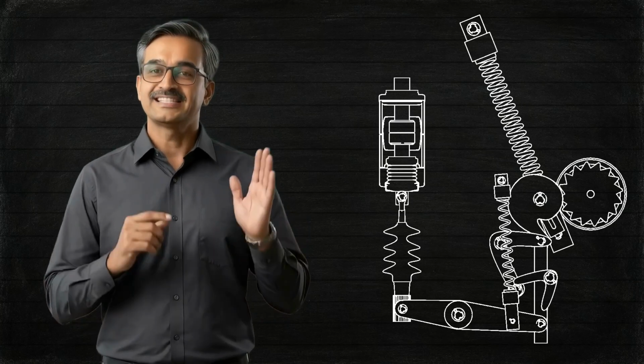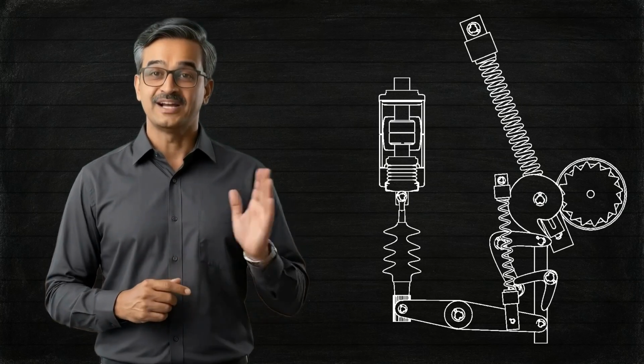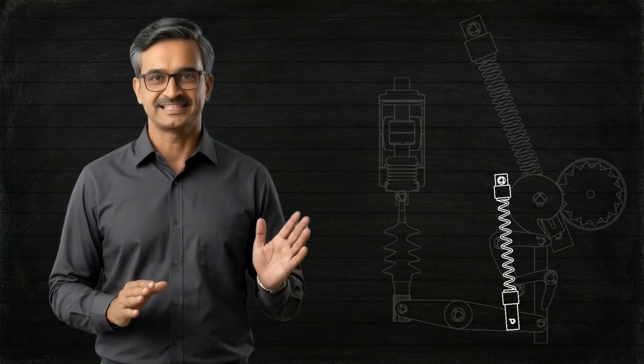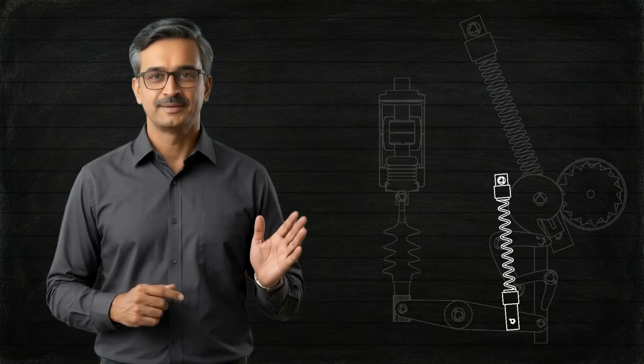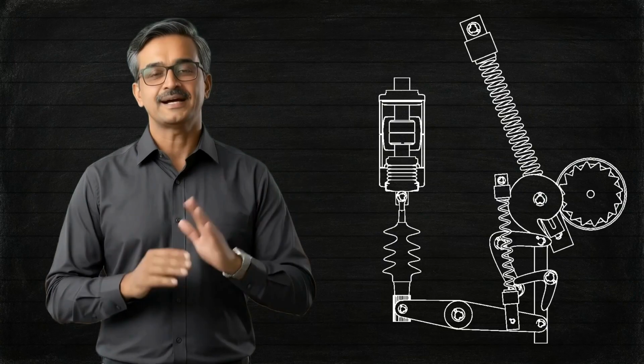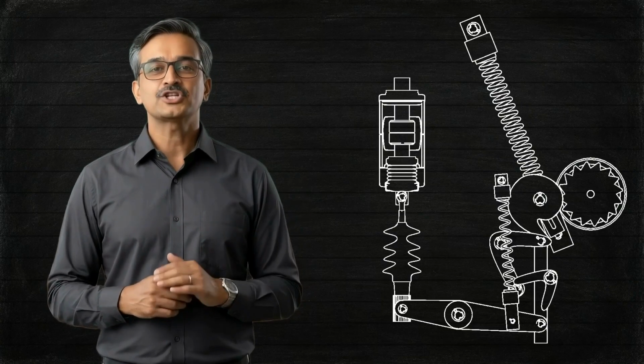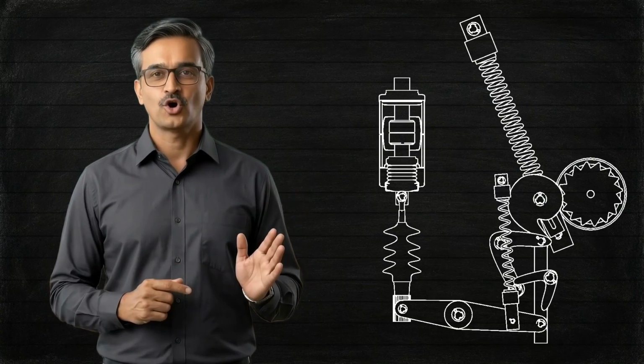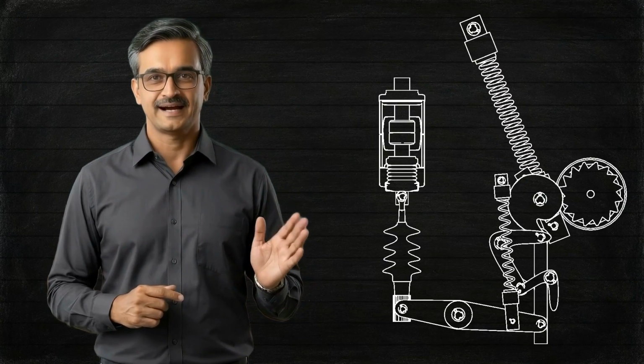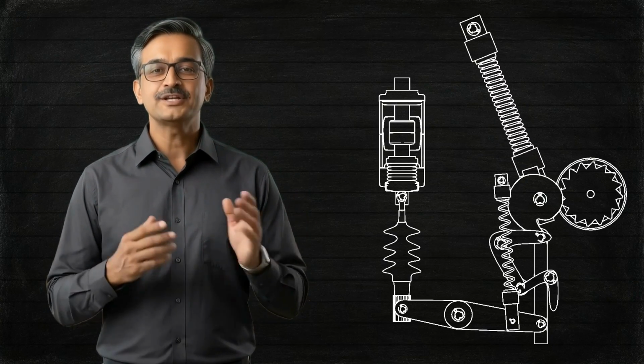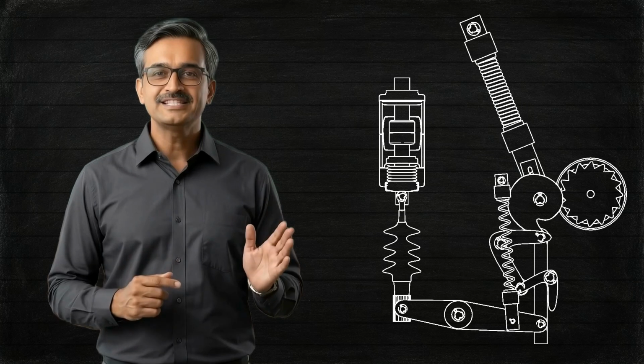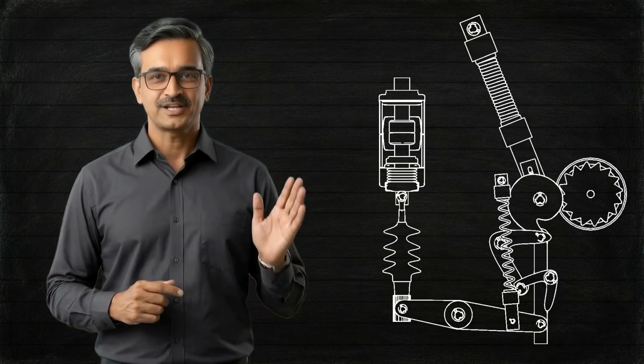But something very interesting happens during this closing movement. As the moving mechanism travels, it simultaneously compresses the second spring. This is the opening spring. So immediately after the breaker closes, the opening spring is fully charged. Then, a limit switch automatically starts the motor again and the closing spring is recharged. In other words, the breaker is now fully prepared for the next tripping operation.